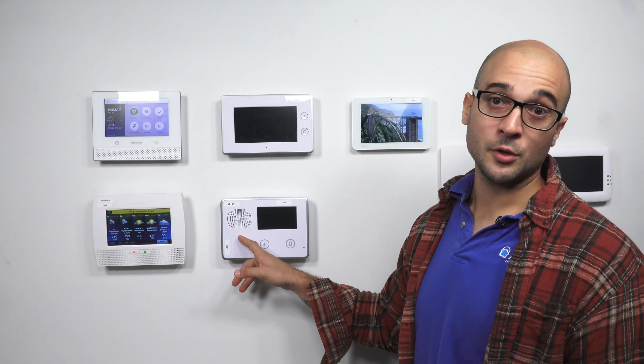The GC2, on the other hand, you actually have to add on a device called the Go Bridge, which allows it to interface with an IP network. It doesn't have a built-in Wi-Fi module, and it doesn't have any other way other than that device to get it communicating on IP. If you do install the Go Bridge on the GC2 though, you can use it in a dual path setup, as this system lets you install an integrated cellular communicator right on the board. That's pretty much how dual path monitoring works.